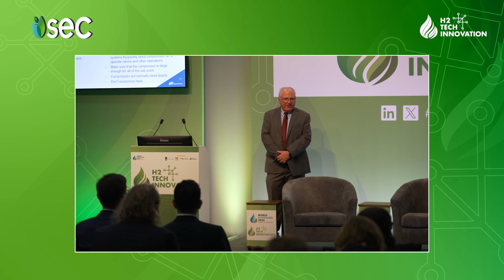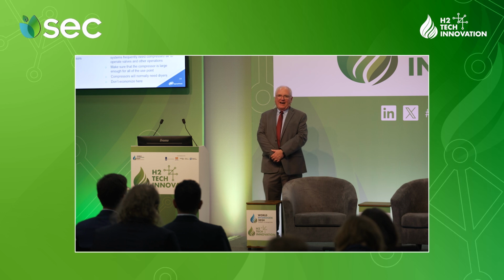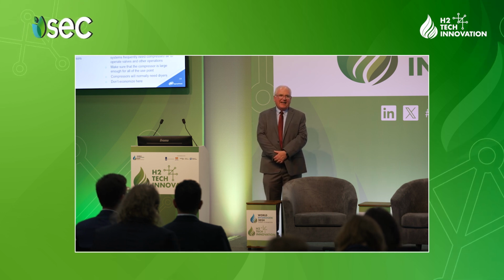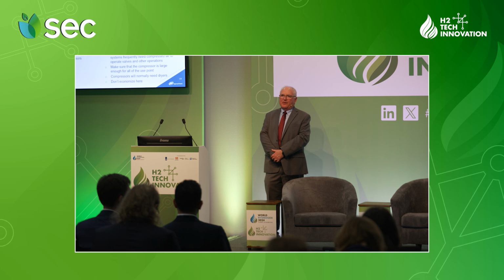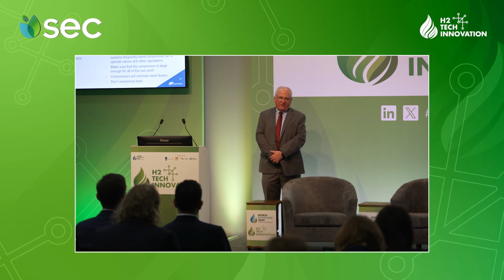Make sure that compressor you get is large enough for your use point. You're probably going to need a dryer with it also. And don't economize here. Working at Haskell, I've dealt with a lot of compressors, and people that economize on their compressors, they come to regret it in the long run. So make sure you get a good rotary screw or better compressor for your system.